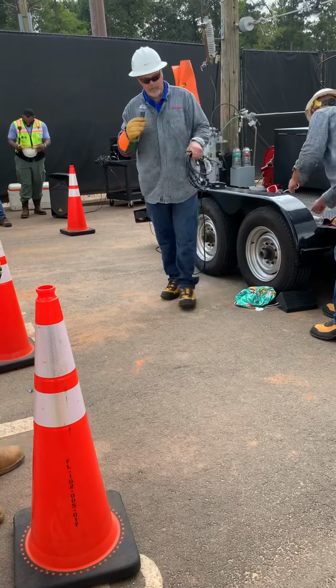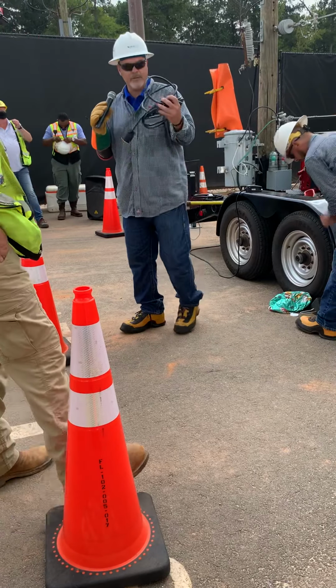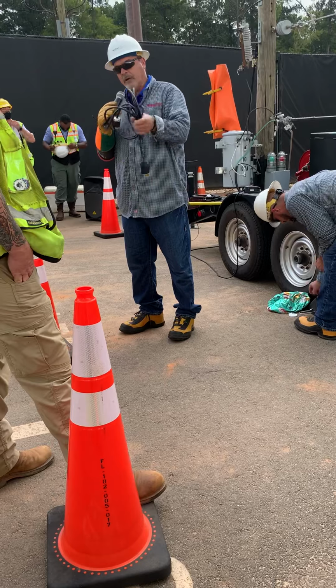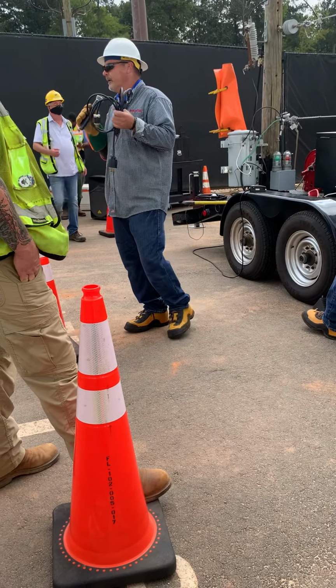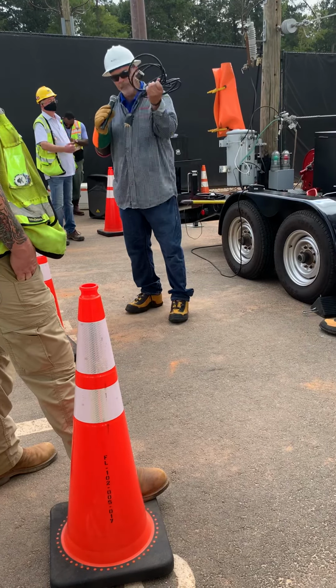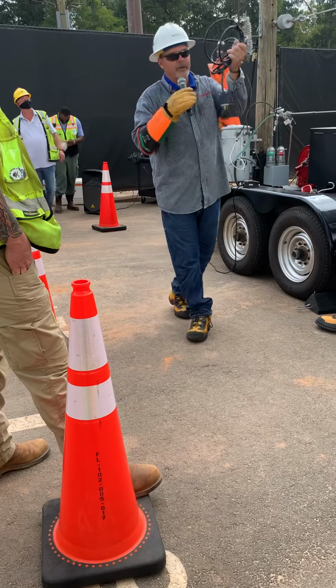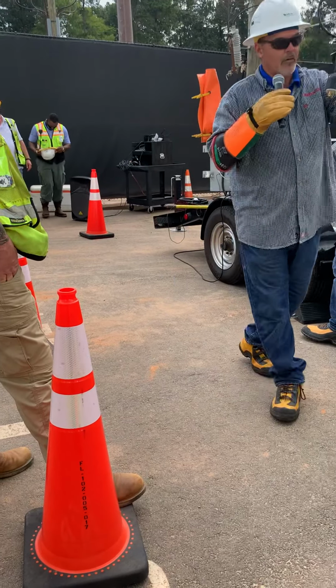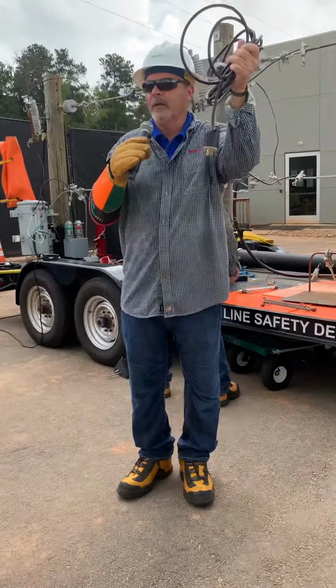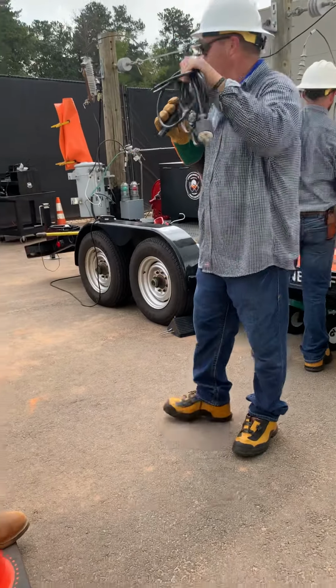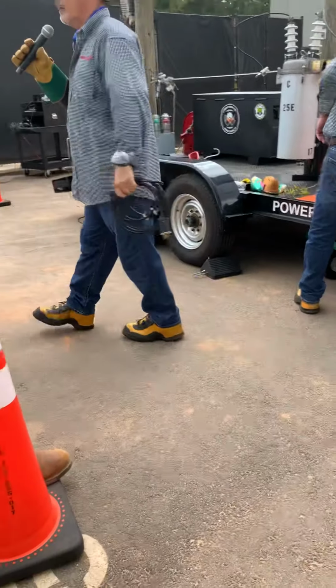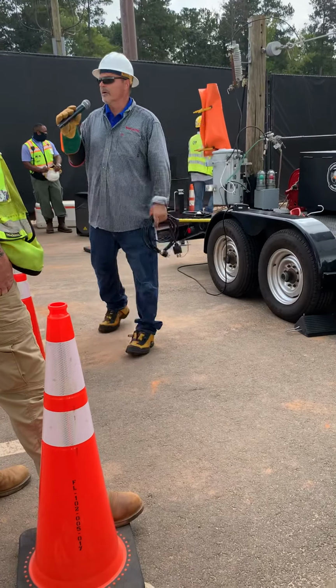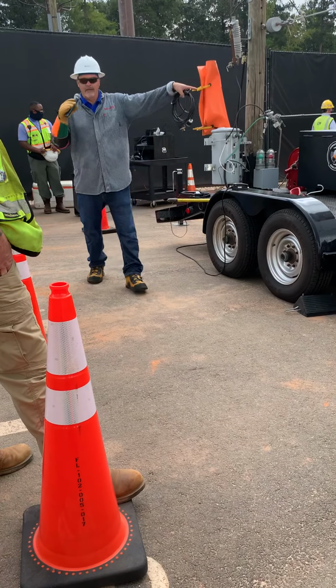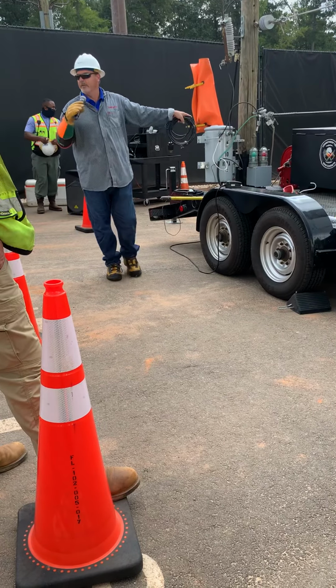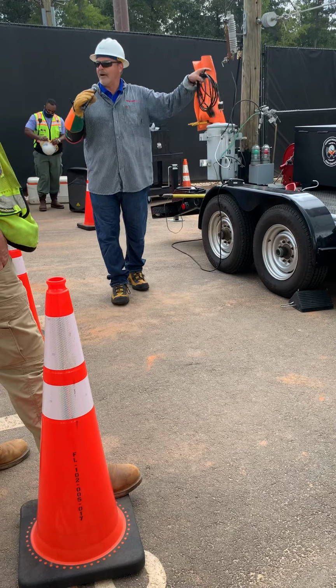But when people go and buy those generators at the home improvement stores, somebody will give them the wise idea to cut the female end off and put another male end on. You can plug it into the generator and plug it into an outlet and have your house on, or get another 220 plug and get the whole house back on. Well, the problem with that is, if you don't cut that main breaker off, or that meter's not pulled, you're backfeeding it out here on this line. That transformer is going to do just like what we said it would do. It's going to take the low voltage and come out high voltage.